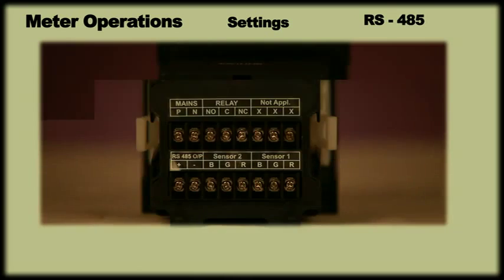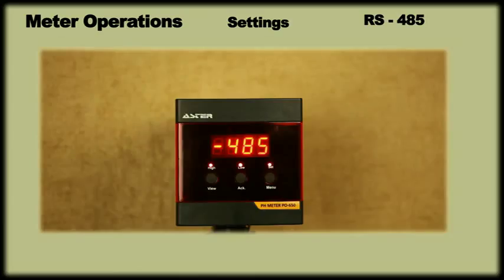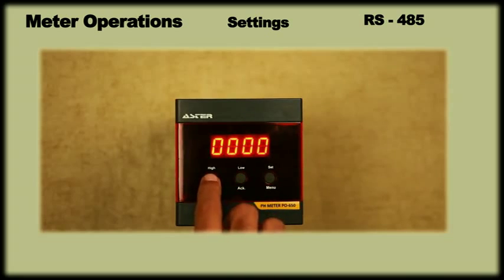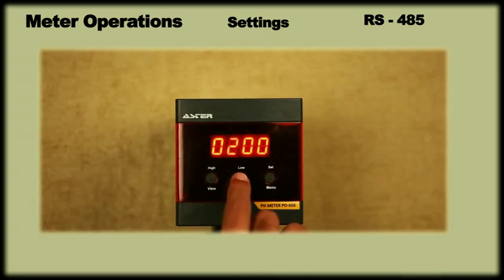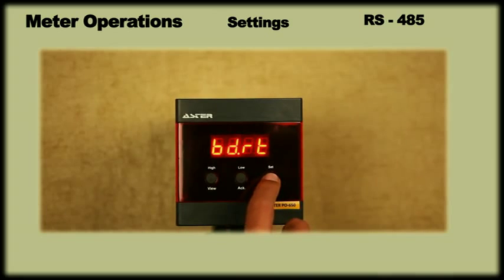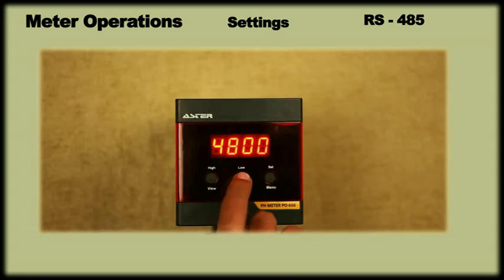Let us now understand the settings for RS485. For meters with RS485 output, only after setting the device ID and the baud rate, one would be able to communicate with the instrument. Let us understand how to do these settings. Press View and ACK keys simultaneously and enter password 0345. Press menu and the display will show baud rate. On pressing the menu key again, the display will show a previously set baud rate. One can select between 4800 or 9600 by using the ACK key.